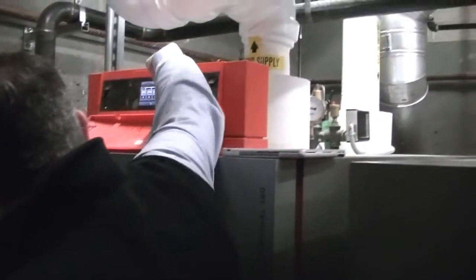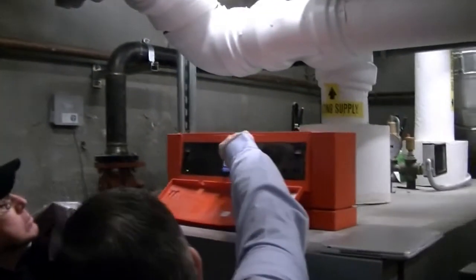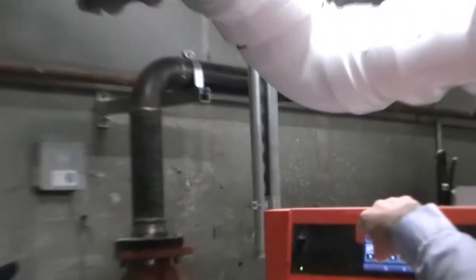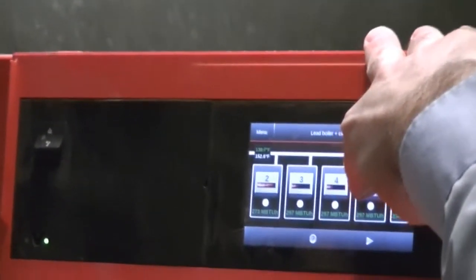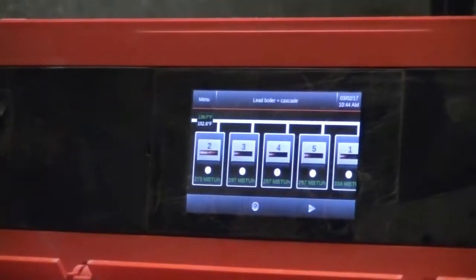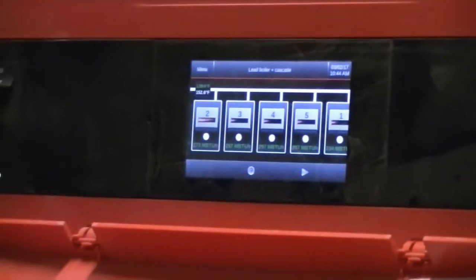If you look down at boiler 1, the thing that differs is you see what all the boilers are doing. If you look at boiler 1, boiler 1 is down here. Boiler 1 has actually become the last boiler in line. And boiler 2 is firing at full input. We don't know the modulation of the cogen, it just has an on or off. And then you can see sort of the modulation range of all the other boilers in the row. This is actually true. It changes.